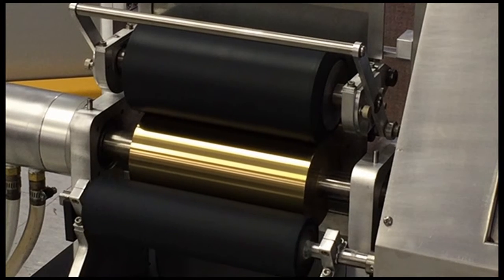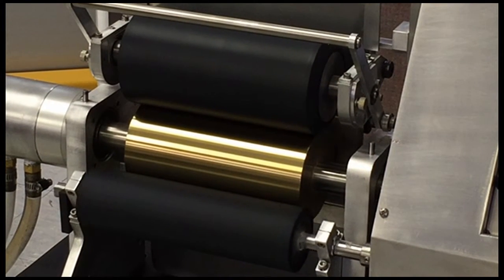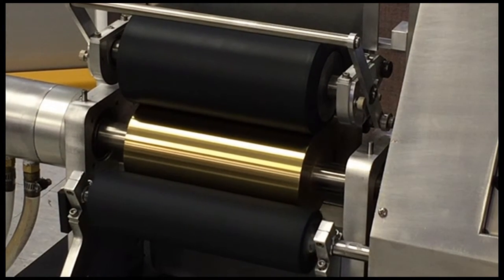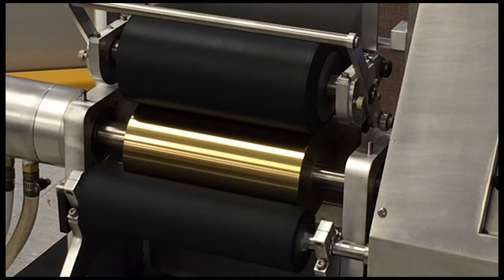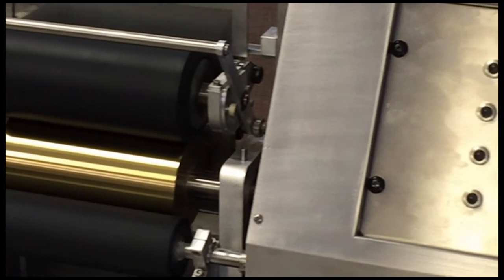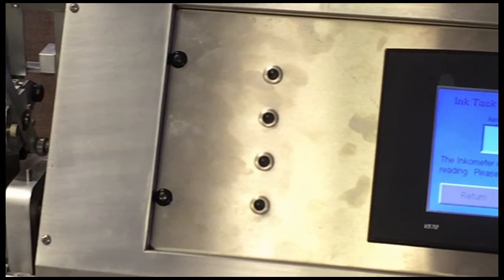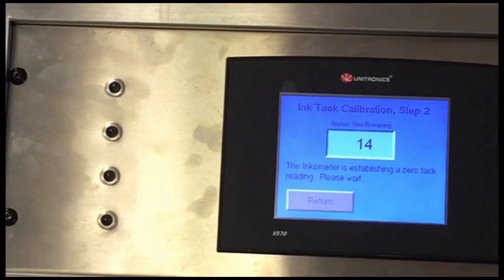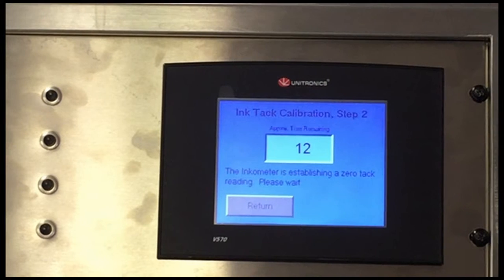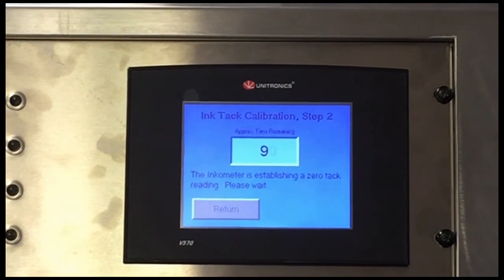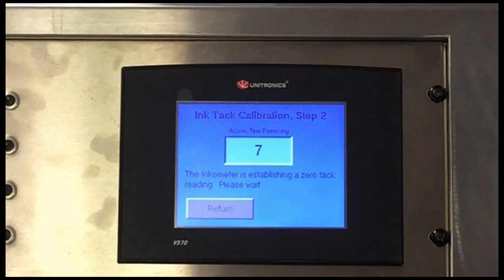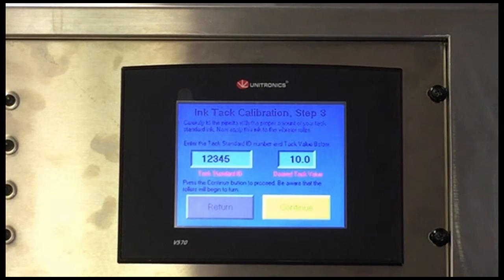Now we've got a little time out here that's telling us how much time will elapse before the next step. What it's doing during that 30 seconds is letting this thing stabilize with no ink under dry conditions and making sure that everything is absolutely rock solid. When this reaches 0, it's going to take that reading off the top roll and call that our 0 reference point. Okay, so that's done.